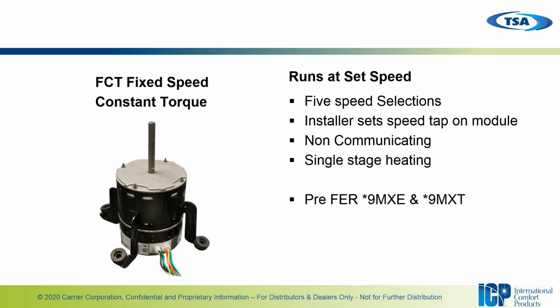And last but not least, we have our fixed speed constant torque motor, or X13 if you will. This is the only motor that currently has the speeds programmed into the motor module. You'll typically have 5 speed selections. However, be cautious because some manufacturers do not program all 5 speeds in the motor.